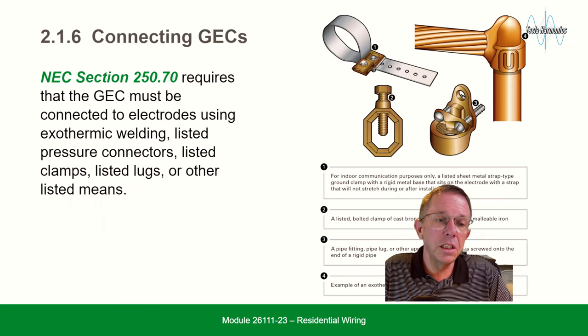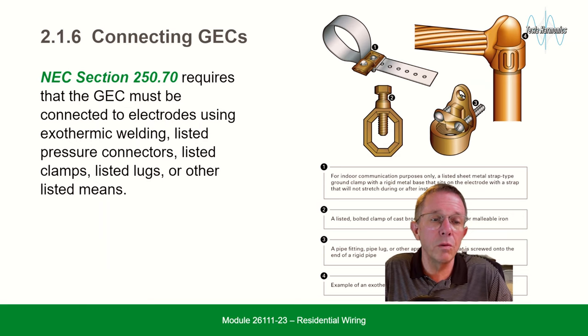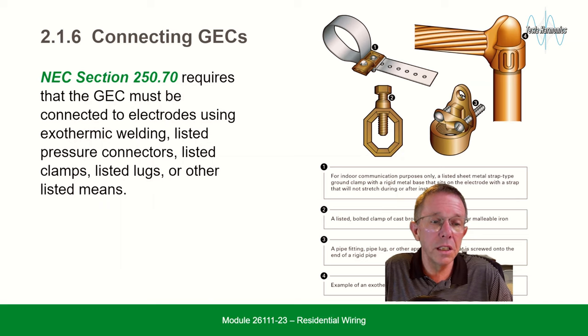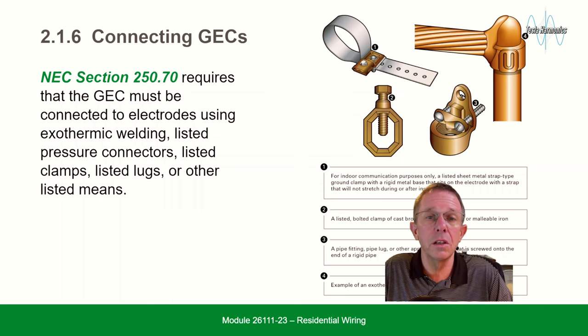Connecting GECs: NEC section 250.70 requires that the GEC must be connected to the electrodes using exothermic welding, listed pressure connectors, listed clamps, listed lugs, or other listed means.